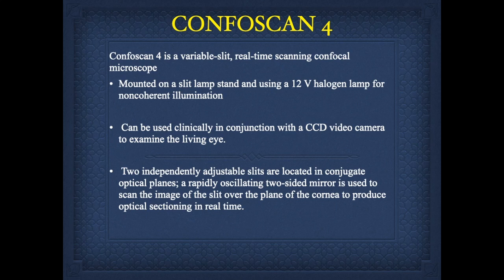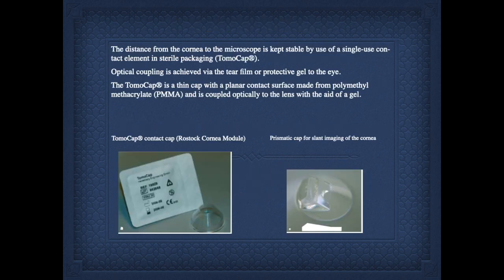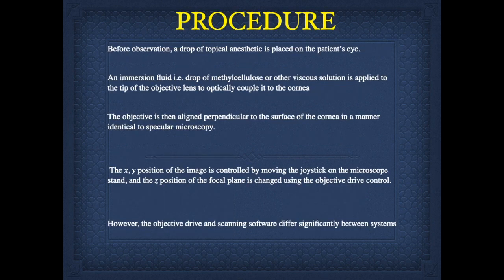Coming to CONFOSCAN4, it is a variable slit real-time scanning confocal microscope. It can be mounted on a slit lamp stand and uses a 12V halogen lamp for non-coherent illumination. This optical cap can be used for contact imaging. For the procedure, a drop of topical anesthetic is placed on the patient's eye and an immersion fluid is applied to the tip of the objective lens to optically couple it to the cornea. This is controlled by moving the joystick on the slit lamp microscope and the Z position of the focal plane can be changed using the objective drive control, hence imaging can be obtained.